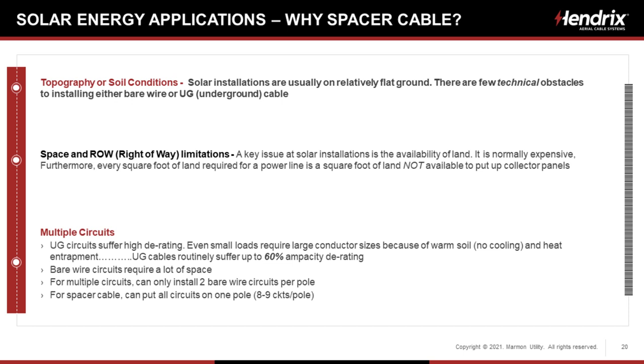How about solar energy? Why would anyone want to consider using spacer cable in a solar energy application? Well, we take a look at topography or soil conditions. Solar installations are usually on relatively flat ground. There are a few technical obstacles to installing either bare wire or underground cable. How about space and right-of-way limitations of solar applications? A key issue with solar installations is the availability of land. It's normally expensive, shockingly expensive. And furthermore, every square foot of land required for a power line is a square foot of land not available to put up panels. So again, we're competing with collection systems versus panels, which seems crazy.